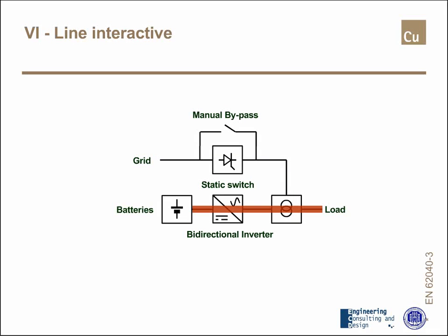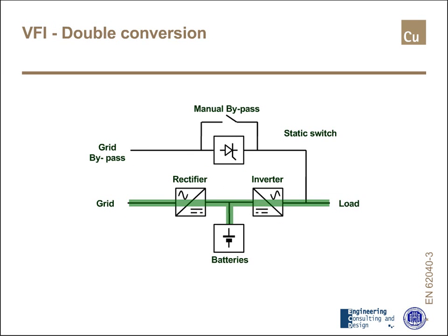Without the grid, the load is fed directly by the batteries. The last type is VFI — voltage and frequency independent — also called double conversion. The scheme is shown in the slide. In the presence of the grid, energy flowing through the green path is converted twice: from AC to DC to charge the batteries, and to supply an inverter that supplies the load.